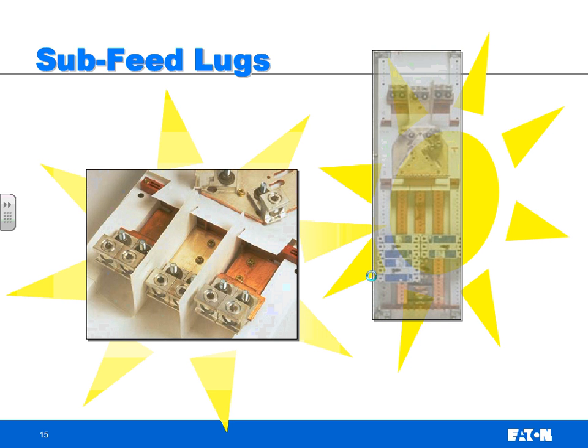Well, I believe a compression lug will maintain its compression over a longer time. Yeah, if you think about the cable, a building, a school is a good example, you run a lot of load during the day, and then at night everything drops down. Cables, being made of metal, copper usually, sometimes aluminum, but mostly copper, have what they call coefficients of expansion. So that copper is going to expand with a lot of current, contract under normal conditions, expand when more current comes through. So every time that expands and contracts, if you think about the mechanical lug, it's going to be inside of that lug, and gradually over time it'll loosen. And so with mechanical lugs, you do probably have more of a susceptibility to loosen over time.